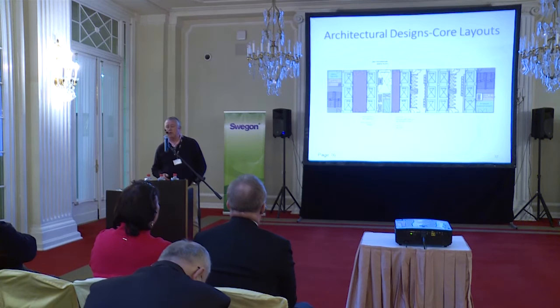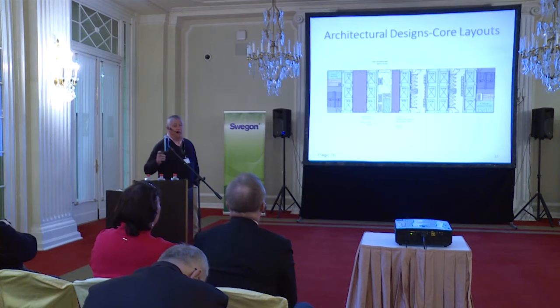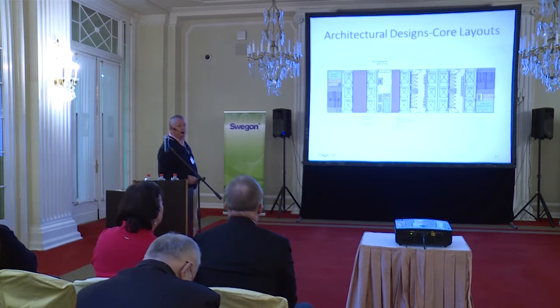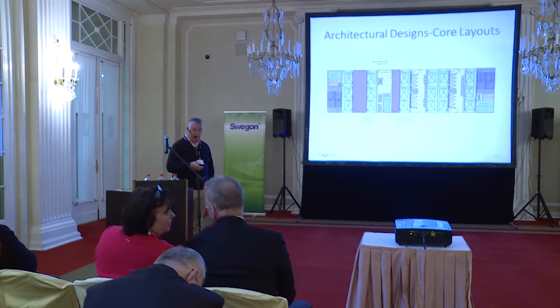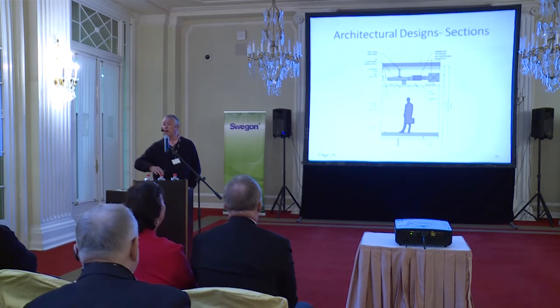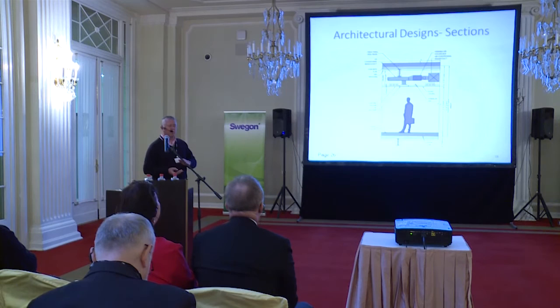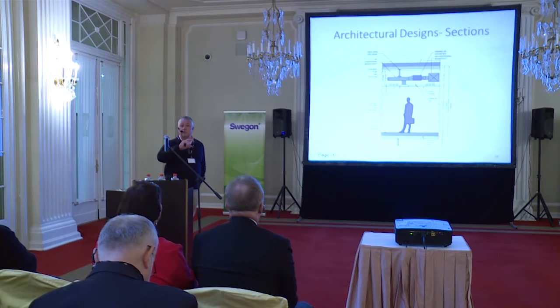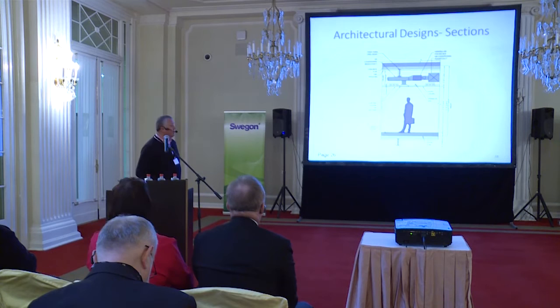What will often happen in Asia, in India, and other places, is the local engineers will get hold of it and say we need spaces on both sides of the core where we can put the mechanical system - and therefore the leasable area on the floor is reduced. Then there's also the floor-to-floor height - when you look at a high building like this, it affects how many floors you can fit in. So if we can start compacting it, by doing radiant ceilings or active beams or just a very efficient overhead VAV system, we can actually reduce the floor-to-floor height by even 100 or 150 millimeters.